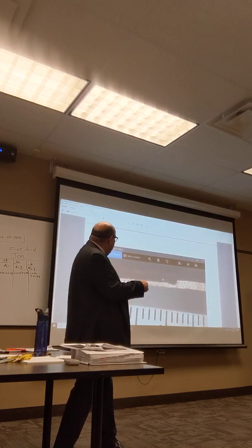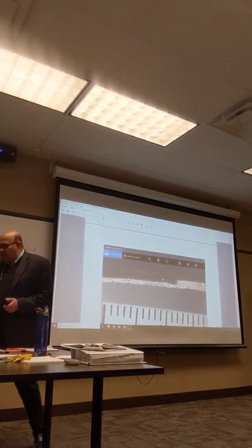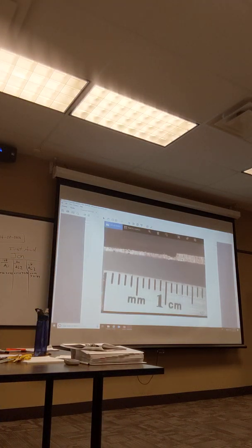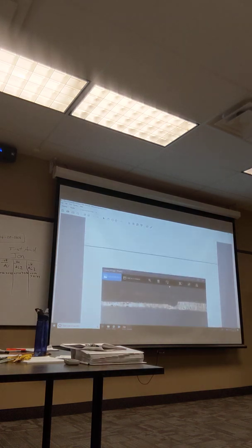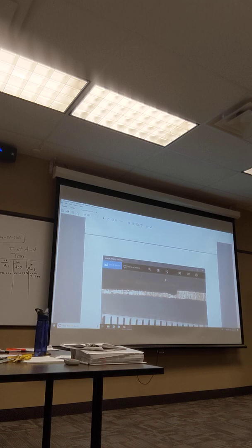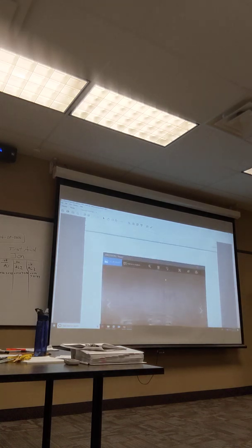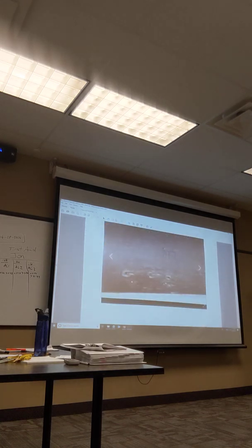And this is the pipe. This is the remainder, it's kind of curving like this. I don't know if I have another picture. So that's the pipe here, and this is the cross section, and this is a zoom on the horseshoe pitting.